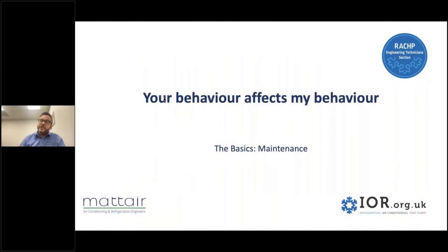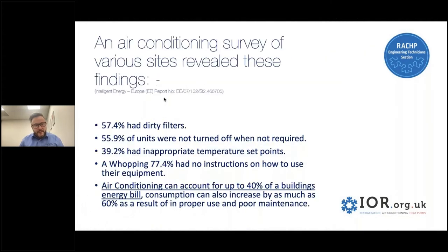What I want to discuss is that your behavior affects my behavior, which might not be what you think, because I want to talk about basic maintenance, which I often think is still overlooked. This report is quite old, but it's still prevalent today. Somebody did a survey of various sites and revealed that 57% had dirty filters, 56% of units were not turned off when not required, there were inappropriate set points, and a lot of them had no instructions on how to use equipment.